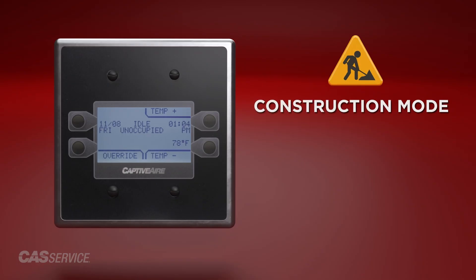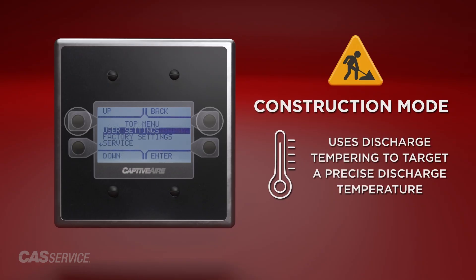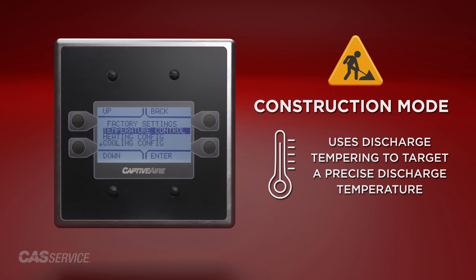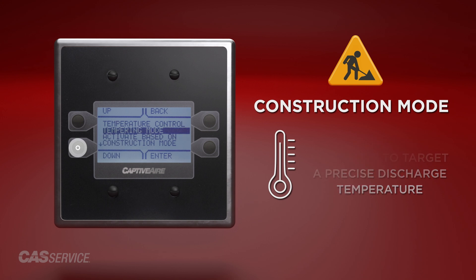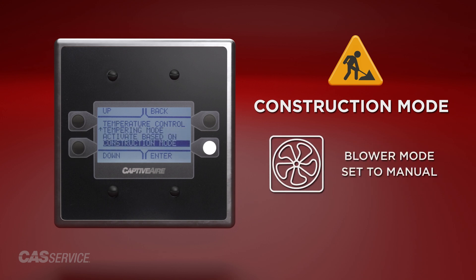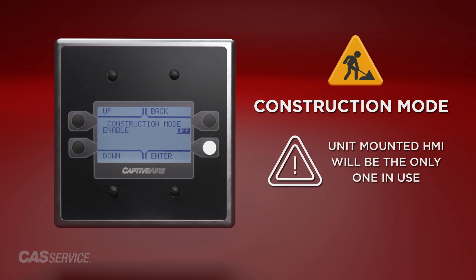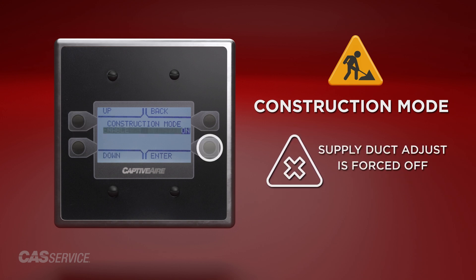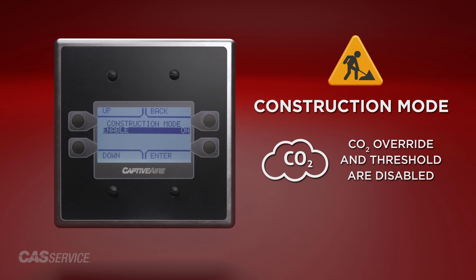Construction mode will use discharge tempering to target a precise discharge temperature and intake activation for a call of either heating or cooling. The blower mode will be set to manual, allowing for an on-off function. The unit mounted HMI will be the only one in use. Supply duct adjust is forced off, and CO2 override and CO2 threshold are disabled while construction mode is enabled.